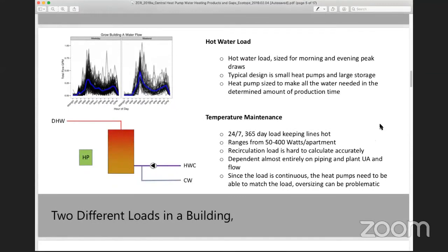One really important thing to distinguish in any central hot water or apartment building is that there are really 2 loads in these buildings. There's a hot water load, the actual heating of the water, which usually corresponds to 2 peak draws, one in the morning and one at night. The second load, which you cannot forget, is temperature maintenance - this is the recirc loop, or keeping the loops hot, and it's a 24/7 load purely dependent on your insulation and surface area. So the game becomes a design optimization, trying to keep those surface areas to a minimum.